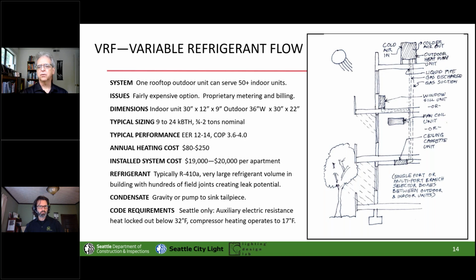So here is a situation where you have a very large volume of refrigerant, and 410A is 2,080 times more global warming potential than CO2, is that right? So it's something you want to consider carefully. It's also, as Ben I think mentioned, a little spendy. It's more like $20,000 per apartment to do this system.